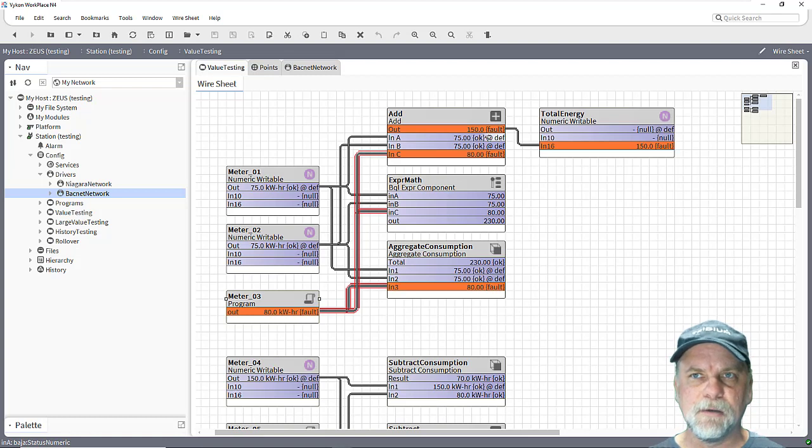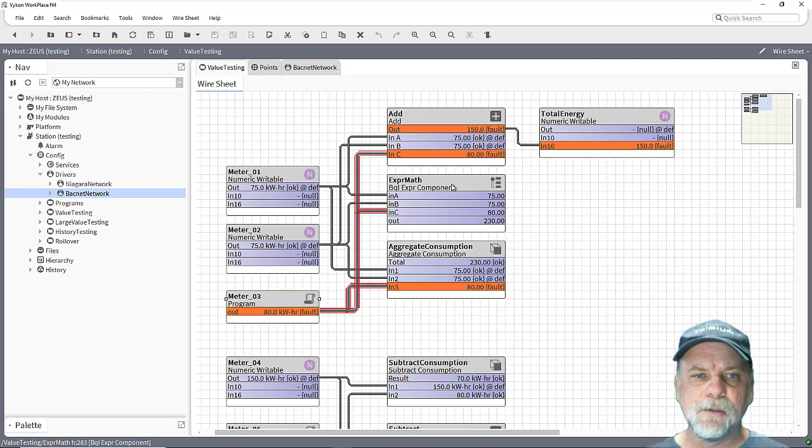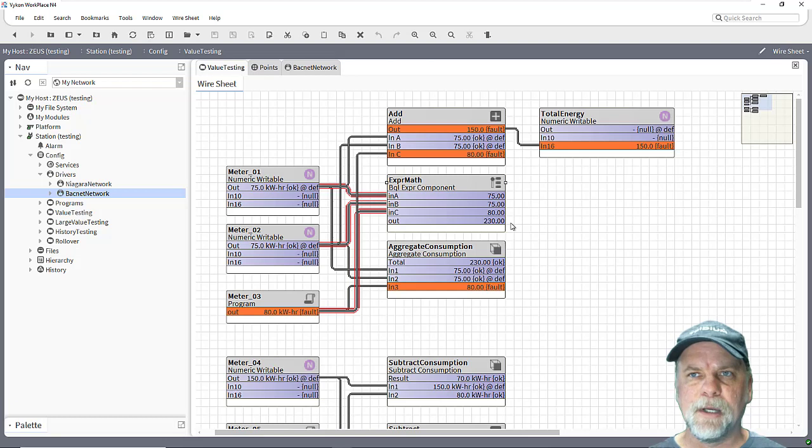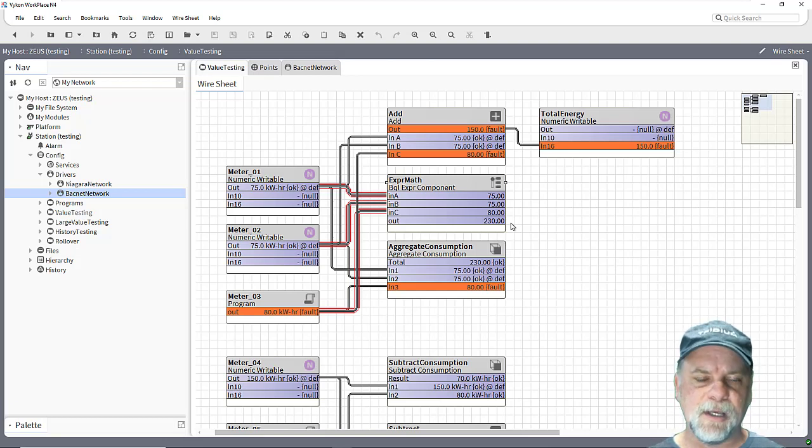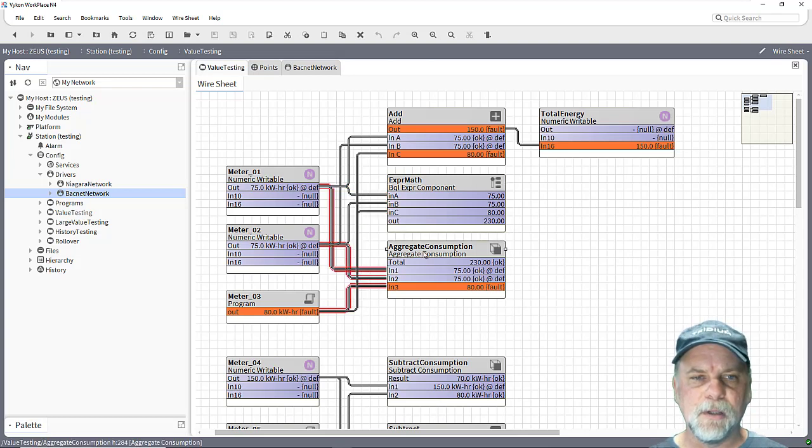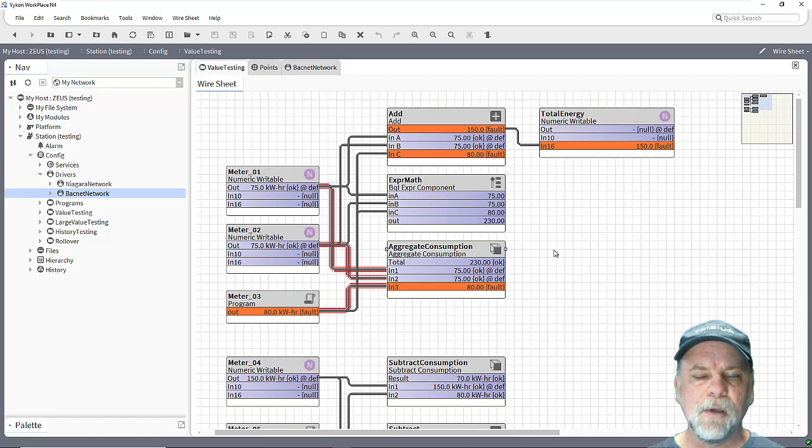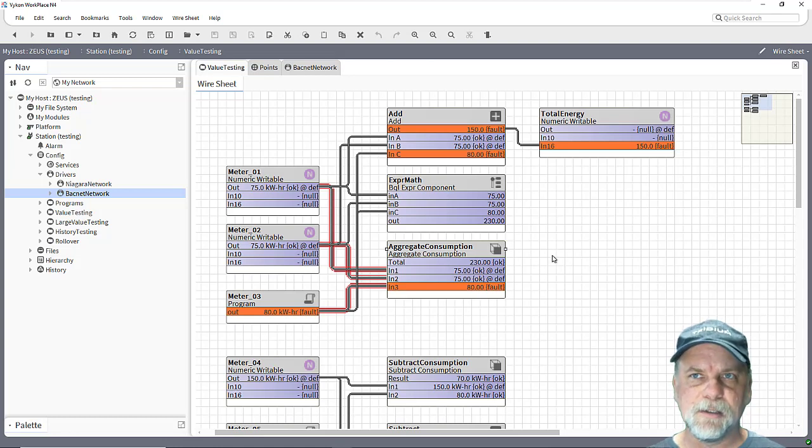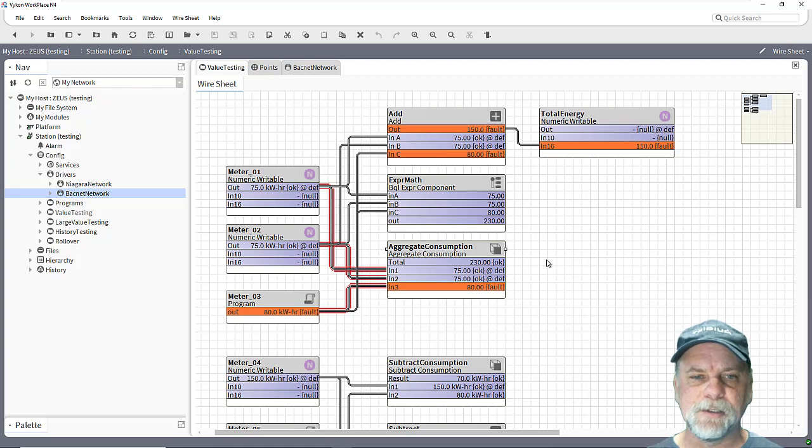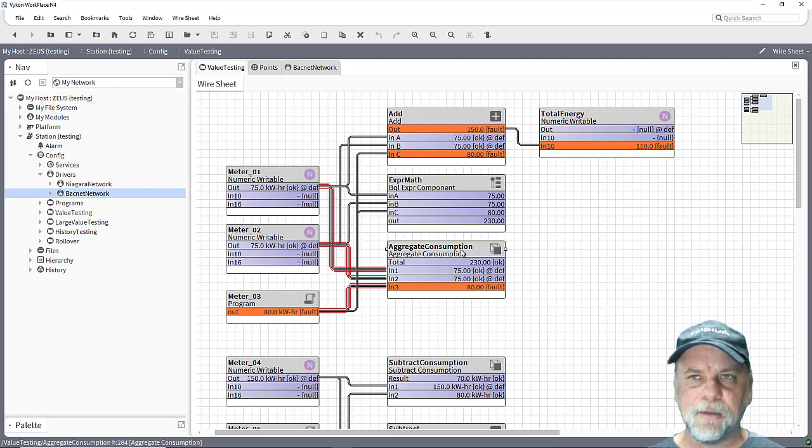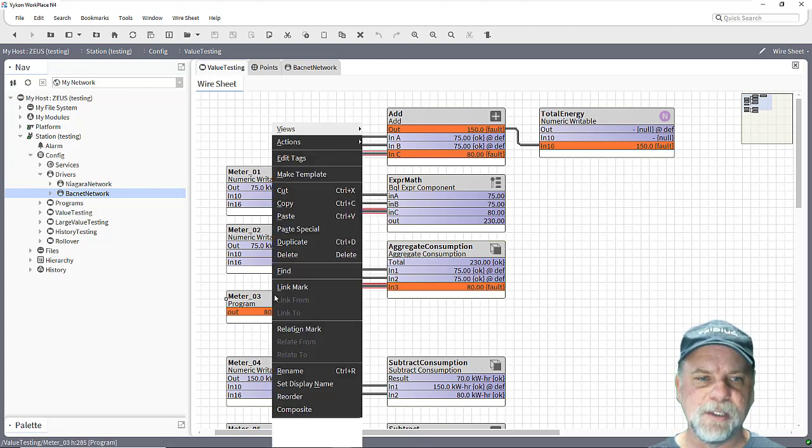You'll notice with the add block that the output here goes to 150. So the add block by default will disregard that invalid status of a fault status there. Using an expression block from kit control you'll notice that the output is still at 230. So the expression math block is not actually excluding that fault status. And this is also a third type of component which comes from the Vykon Pro module. It's an aggregate consumption block and it's designed when it has an invalid input on the status that it maintains the last known good value in the calculation. So the output of the calculation is still 230.